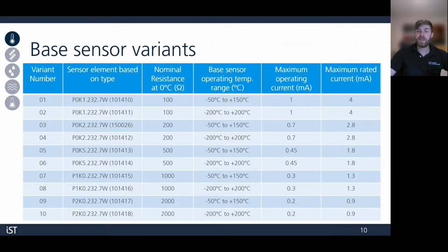Here's an overview of the different base sensor variants that we have on the ESA QPL. We have increasing resistance as we go down the list from 100 to 2000 ohms. The higher the nominal resistance, the bigger the resistance increase you'll get per degree Celsius. If you're doing a 2-wire measurement with long cables, the higher resistance can certainly be beneficial because the wire resistance offset will have less of an effect on your overall resistance measurement. The measuring current should be kept lower with the higher resistance chips to avoid sensor self-heating effects.